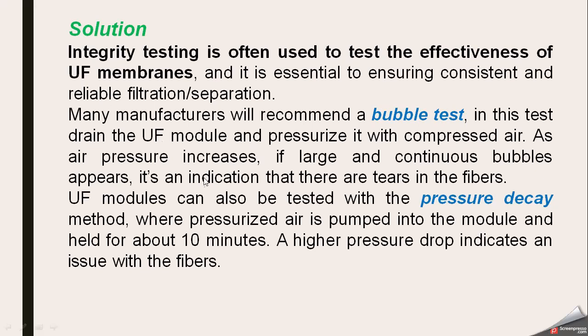As air pressure increases, if large and continuous bubbles appear on the surface of the membrane, it is an indication that there are tears in the fibers, and that's why it is not working properly. So basically in the bubble test we are just pressurizing the membrane and checking from where, due to air pressure, bubbles are coming out.